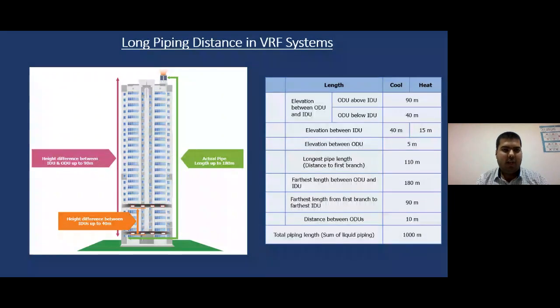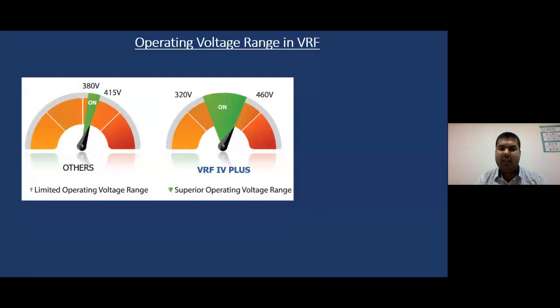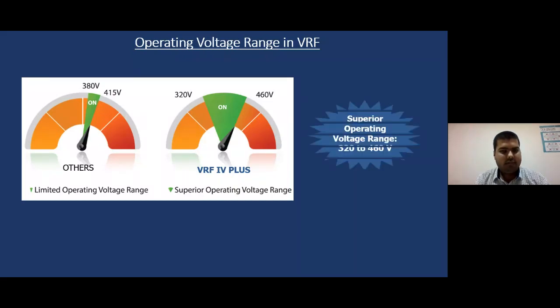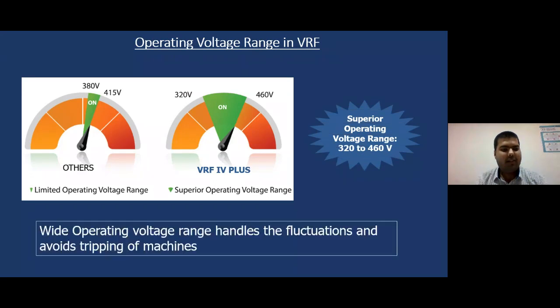So what is the operating voltage range in VRF? It is 320 to 460 volts as compared to the normal range of 380 to 415 volts. Normally, in case of voltage fluctuations, most machines trip and need repairing. A VRF can handle a huge voltage range of 320 volts to 460 volts. A wide operating voltage range handles the fluctuations, which avoids the tripping of machines.